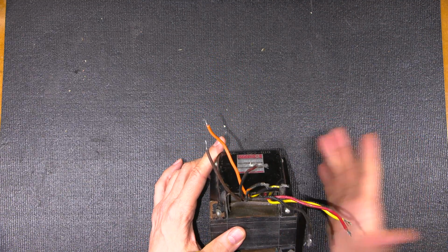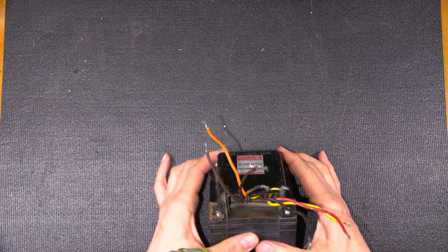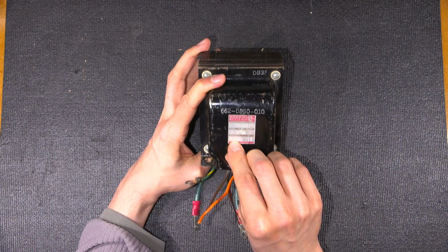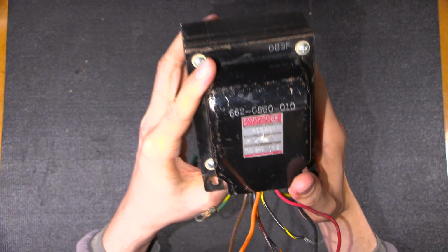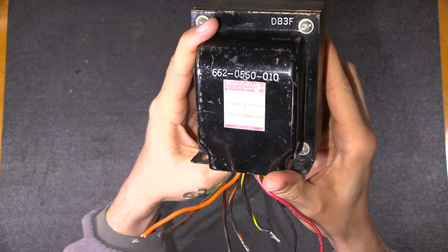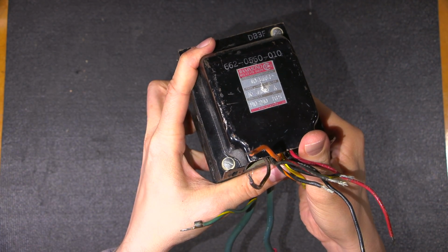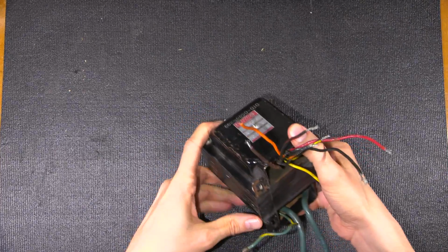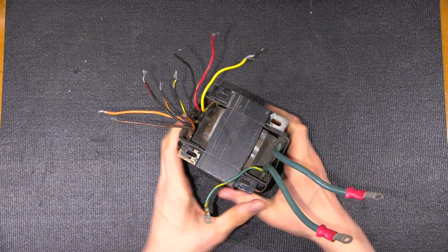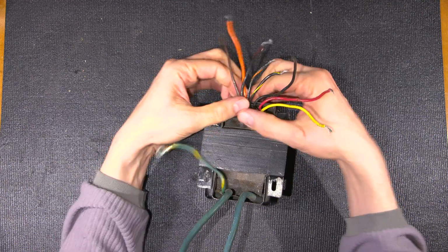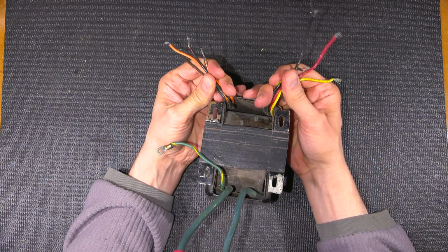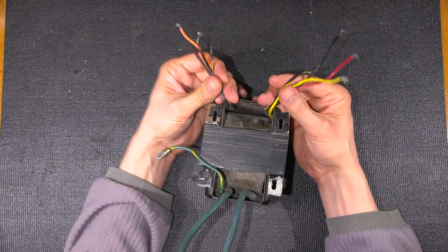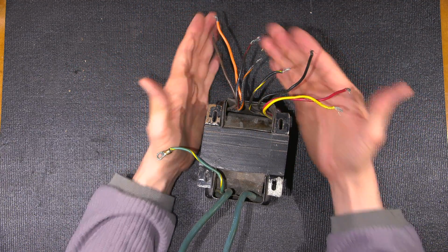First of all, we want to use all the clues that we can get from the transformer itself. So if we read the tag here, it says 110 to 240. You can see that on the tag there. Kind of glary under the light there, it is 110 to 240. So we know that since this is 110 to 240, there's a really good chance at this point that we have two primary windings. So if we were to run this at 110 or 120, say, we would run the windings in parallel.